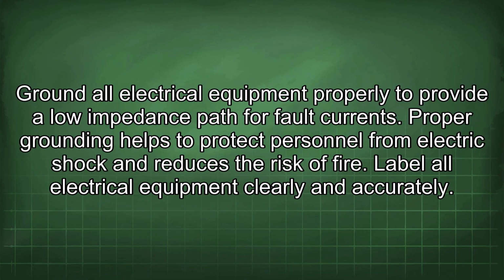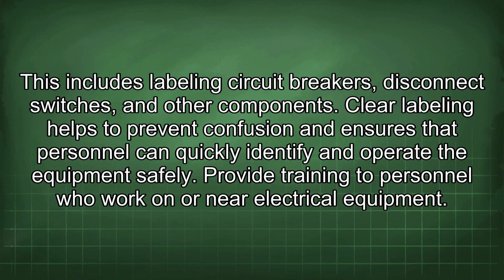Ground all electrical equipment properly to provide a low impedance path for fault currents. Proper grounding helps to protect personnel from electric shock and reduces the risk of fire. Label all electrical equipment clearly and accurately. This includes labeling circuit breakers, disconnect switches, and other components. Clear labeling helps to prevent confusion and ensures that personnel can quickly identify and operate the equipment safely.